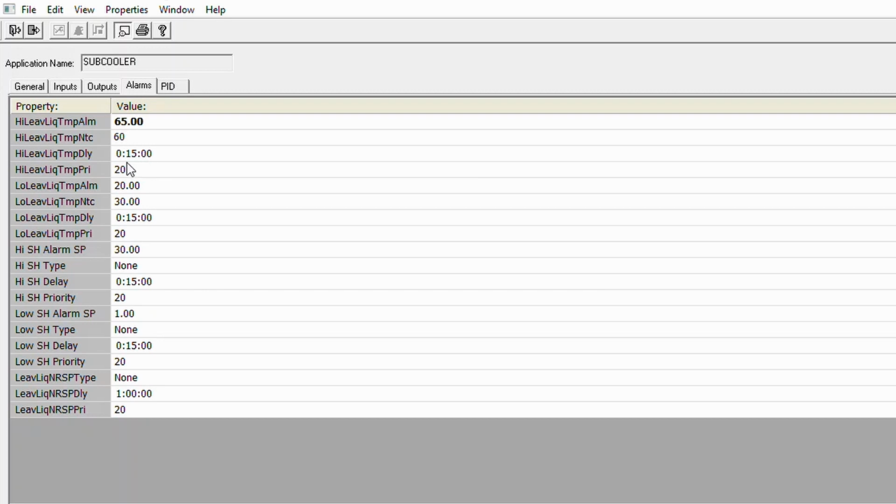If your liquid temp is 65 degrees for say 30 minutes and your subcooler is not working for that long, there's obviously something wrong. Low on gas, I mean subcooler issues. I'd rather catch it now than have 5 techs go there and adjust valves because the subcooler is not working. So having an alarm in a subcooler is a great idea.